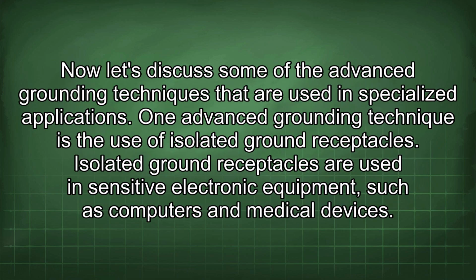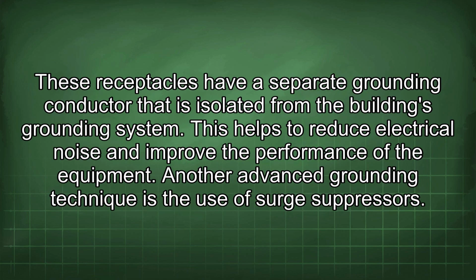Now let's discuss some of the advanced grounding techniques that are used in specialized applications. One advanced grounding technique is the use of isolated ground receptacles. Isolated ground receptacles are used in sensitive electronic equipment, such as computers and medical devices. These receptacles have a separate grounding conductor that is isolated from the building's grounding system. This helps to reduce electrical noise and improve the performance of the equipment. Another advanced grounding technique is the use of surge suppressors.